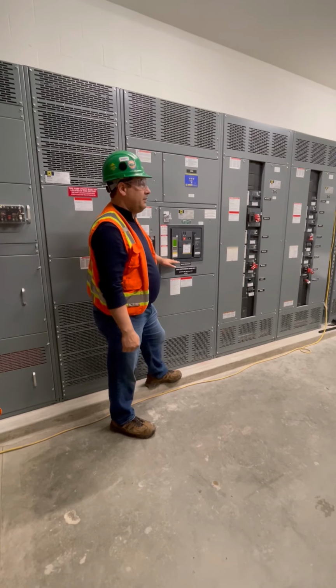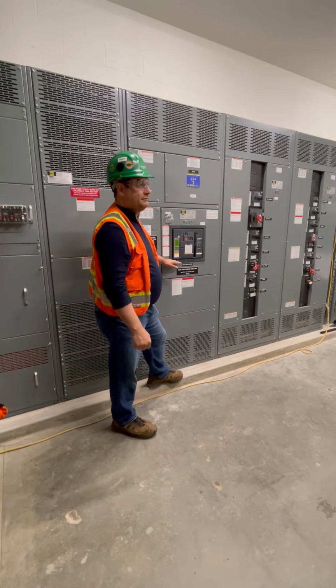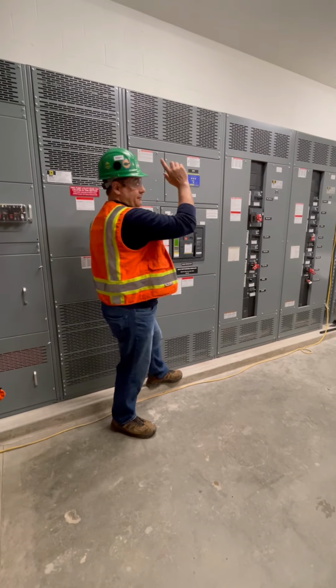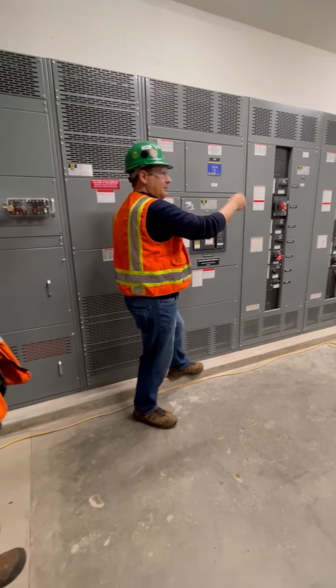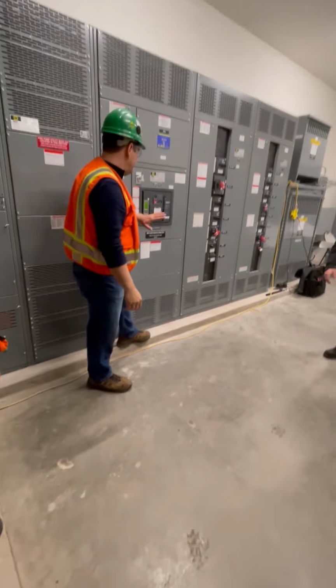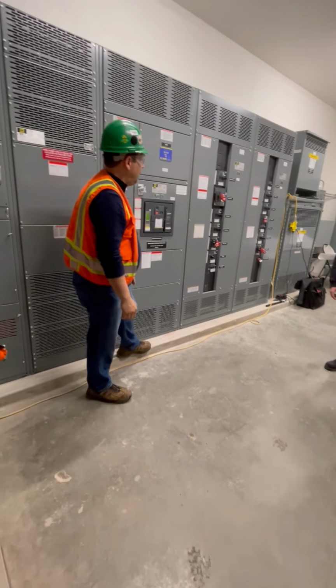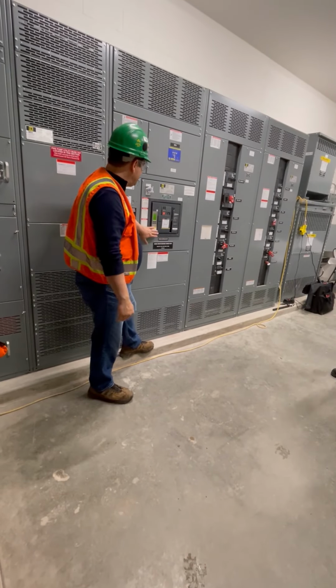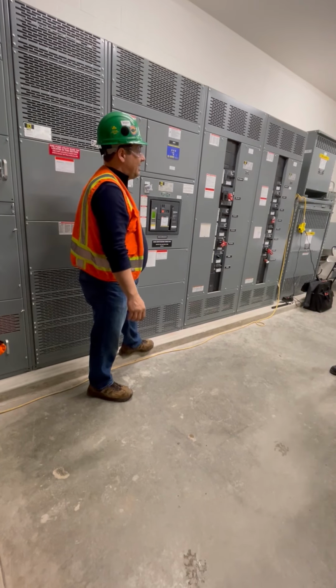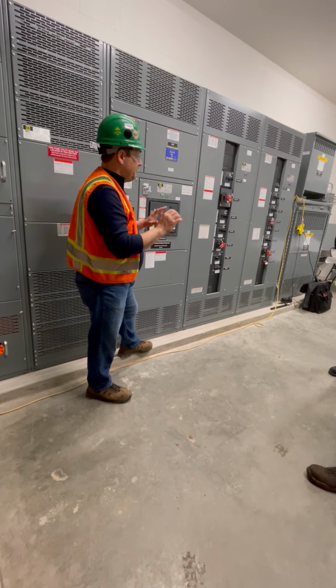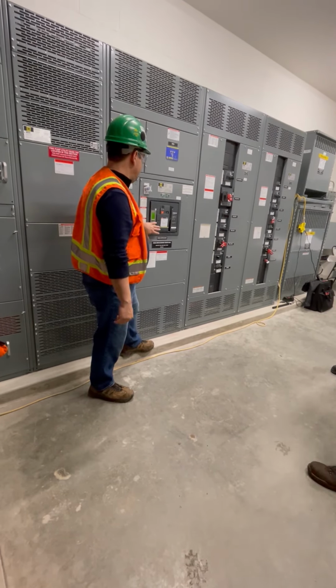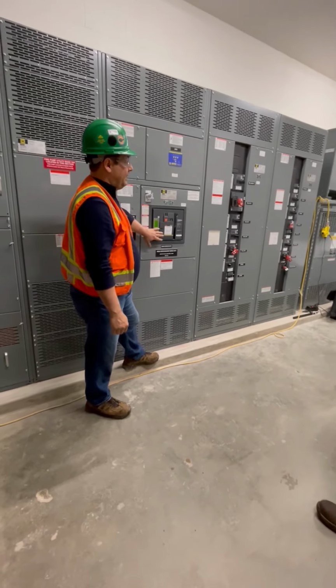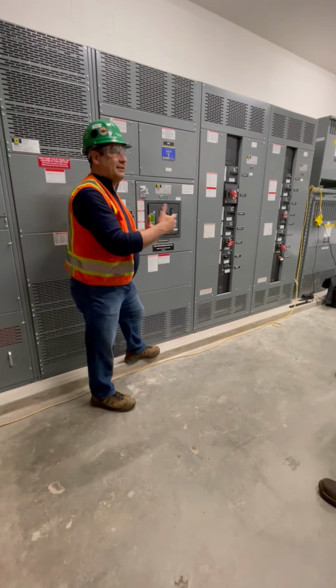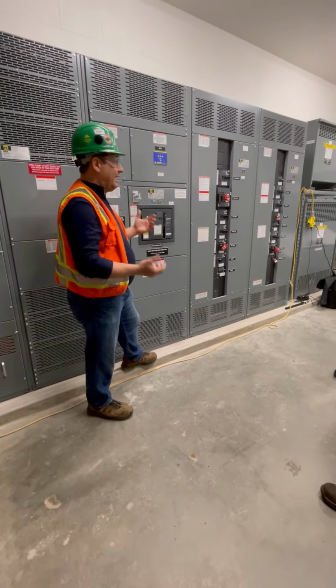This one reaches that level, it's pretty quick. So it could be that you have a ground fault way downstream that created enough of a magnitude of a fault to trip this breaker, right? Now, a pointer: if that happens, what I tell customers to do is, because trust me, I've been through it, the customer is under stress to get the building back online and they don't know what tripped it.